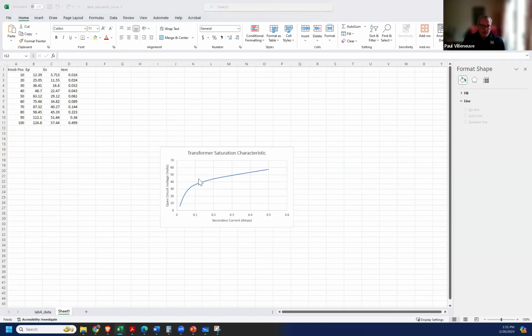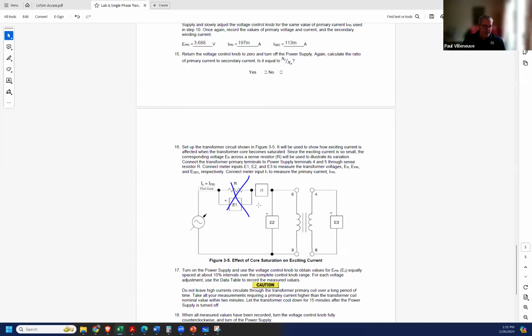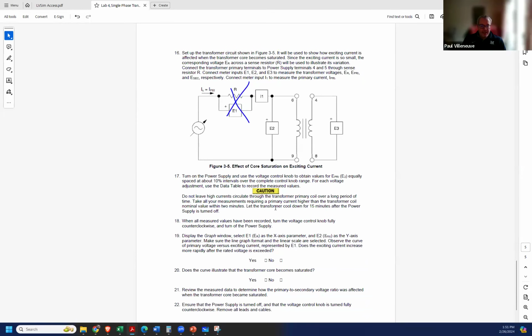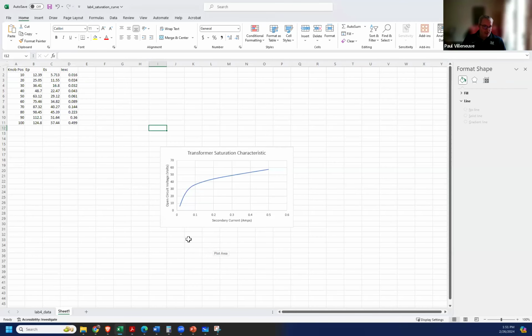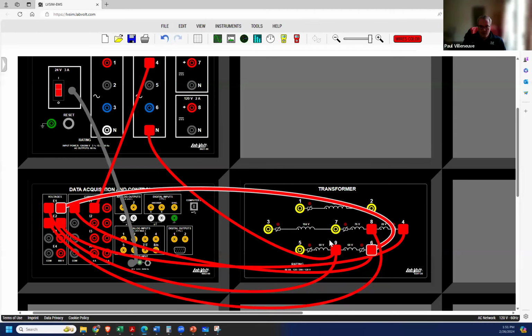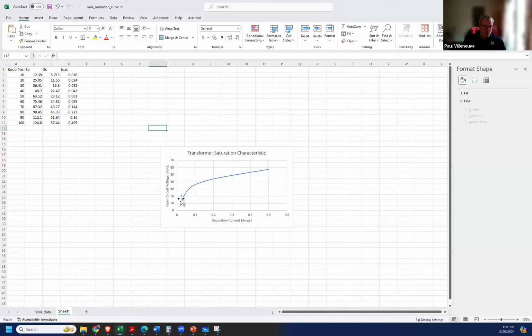So now back to my handout. The question is, does the exciting current increase more rapidly after the rated voltage is exceeded? The rated voltage for the winding is 28 volts. If we get to around 28 volts, right about here, you can see it starting to peel off quite a bit.